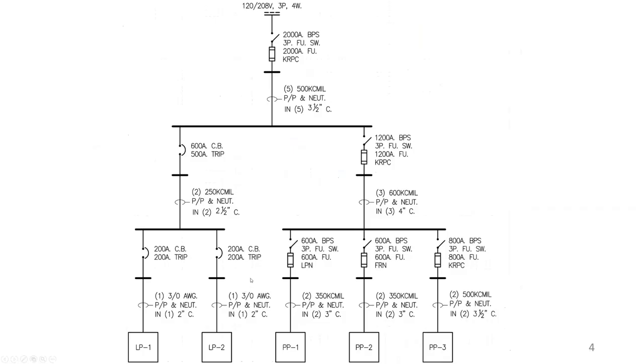Now, going back to this one line, just as a simple example, if I have a 2,000 amp service disconnect and I'm going to feed a 1,200 amp device, if I'm looking at selective coordination, which in some jurisdictions, such as New York City, is required, that's mandatory, is that going to be selectively coordinated? Probably not. The manufacturer's published data tells you that you need a 2-to-1 ratio. Realistically, when there's a fault, it will be lower because it will be a line-to-ground fault. It may also be downstream in the panel board or in the middle of the feeder. But we have to consider all of it. Now, changing this design will dramatically affect two things. It'll dramatically affect the price and the cost of the equipment. It'll also affect the arc flash hazard.